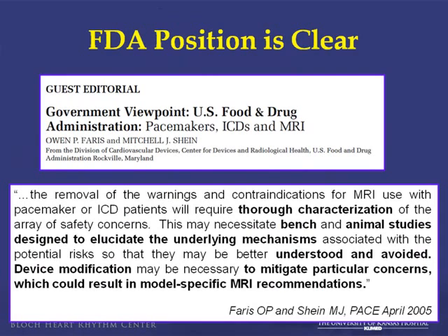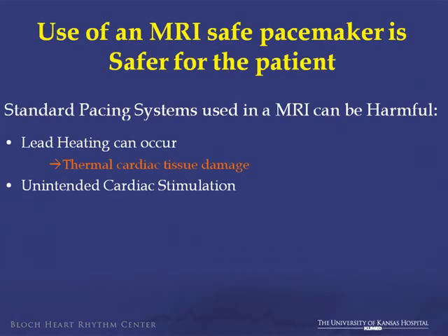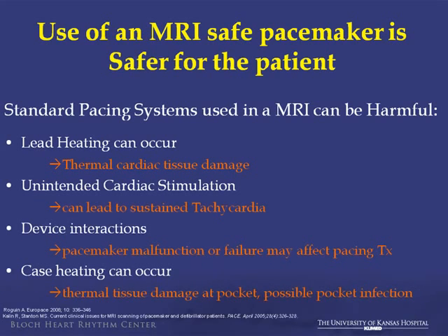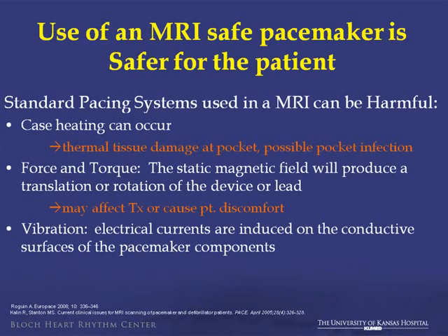The FDA position is also very clear. The only way to consider an MRI-safe device for approval is with proper testing. There are roughly three areas that create an electromagnetic field in an MRI: a static field, a gradient field, and an RF field. These cause issues with heating and other problems. Lead heating can cause thermal cardiac tissue damage, usually at the tip. Unintended cardiac stimulation can lead to sustained tachycardia. The device can malfunction and affect programming, and the case can heat causing issues with the pocket.